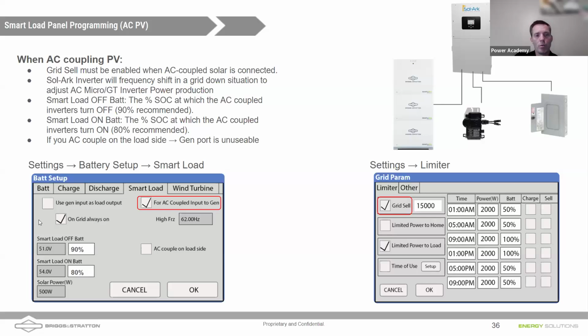Now, as we mentioned earlier, we don't want to overcharge our batteries, and we cannot slow down the charge rate with AC coupled solar like we can with DC coupled solar. So the best we can do is just shut it off. And so we want to make sure that we shut off battery charging in a grid down event from the AC coupled solar when those batteries are above 90%. What this will do is disconnect that AC coupled solar when those batteries are above 90%. But if the on-grid always-on box is checked, as long as the grid's there, the excess charge will flow back to the grid. So we want to make sure that we shut that off at a reasonable value. If you have a very large battery bank with a smaller AC coupled array, you could maybe increase that value a bit, up to 95% or so.